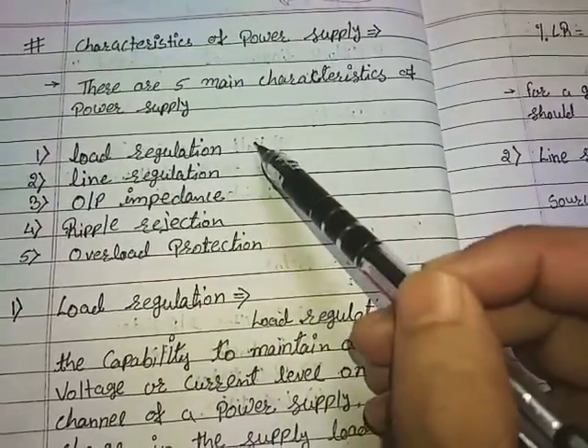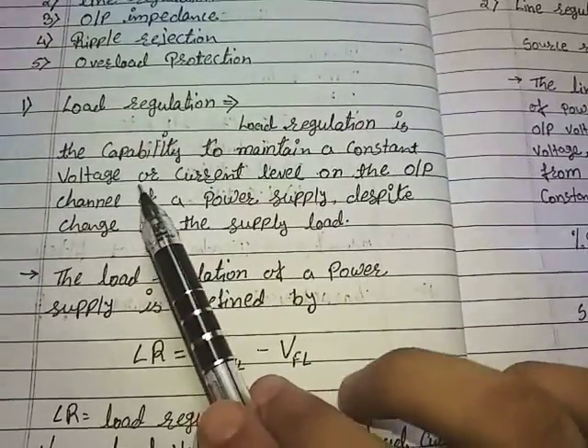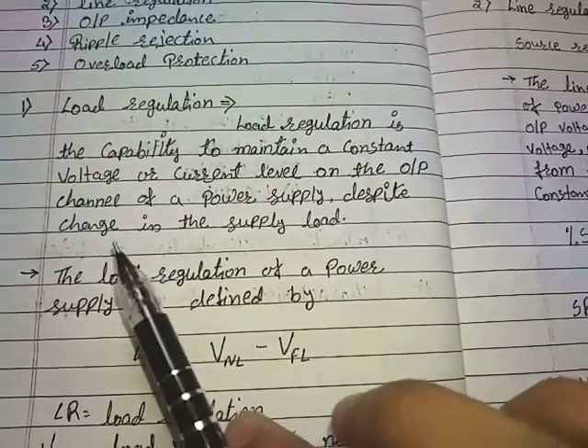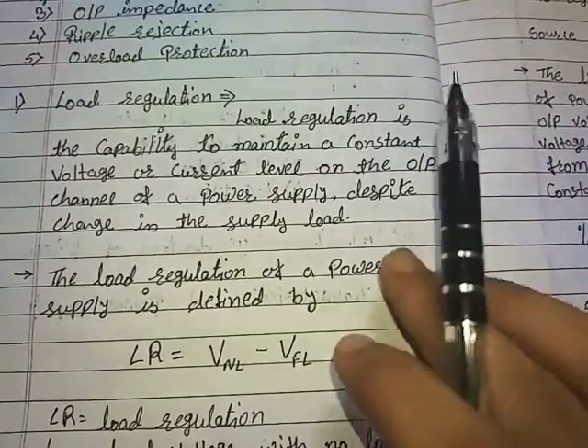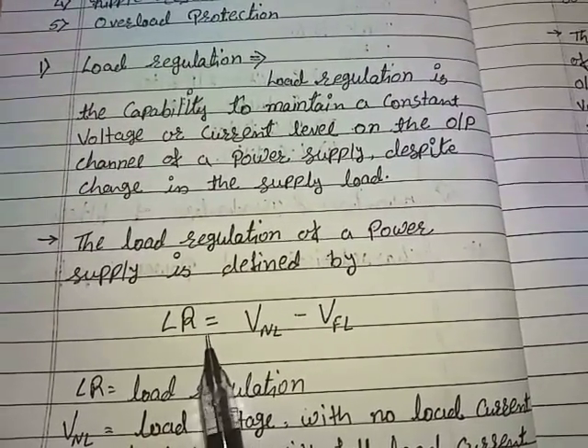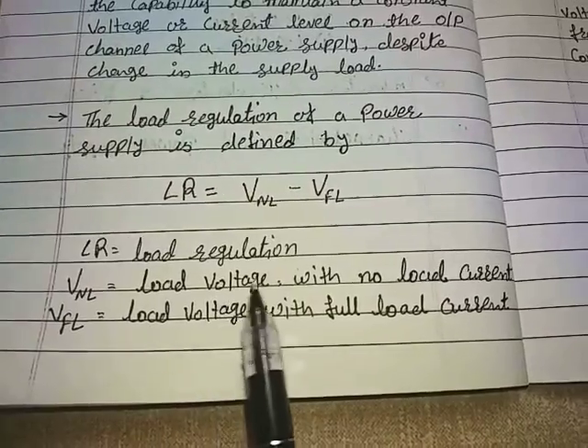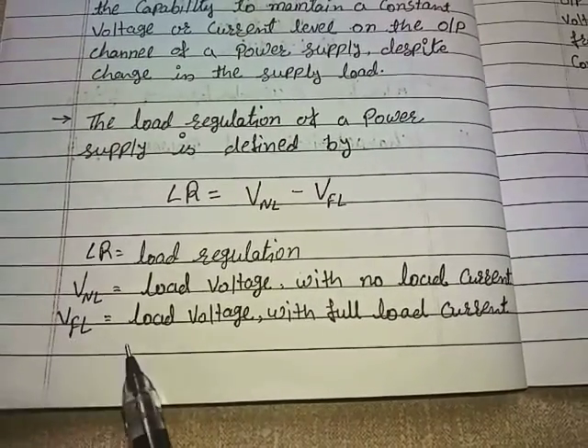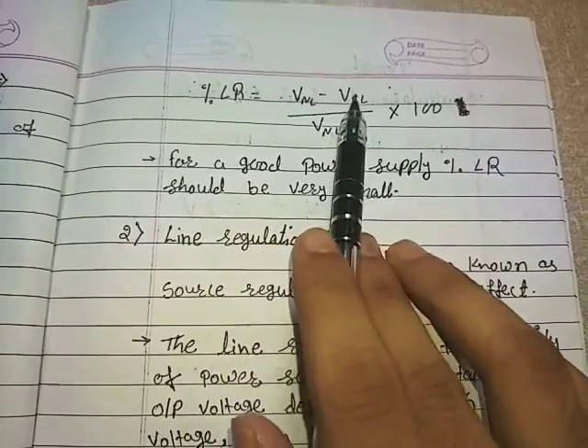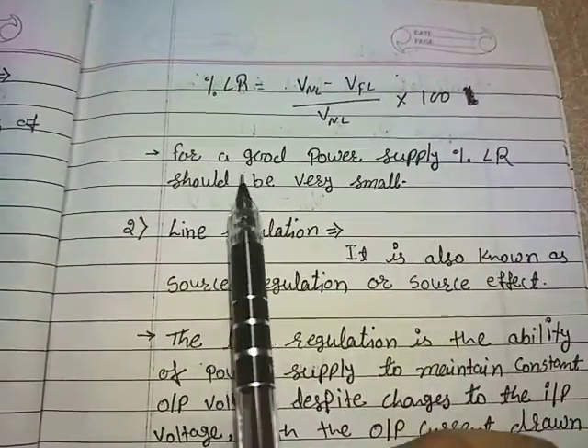Let's start with load regulation. Load regulation is the capability to maintain a constant voltage or current level on the output channel of a power supply despite changes in the load. Load regulation is defined by LR, where LR = VNL − VFL. VNL is the load voltage with no load current and VFL is the load voltage with full load current. The percentage LR is given by (VNL − VFL) / VNL × 100. For a good power supply, percentage LR should be very small.